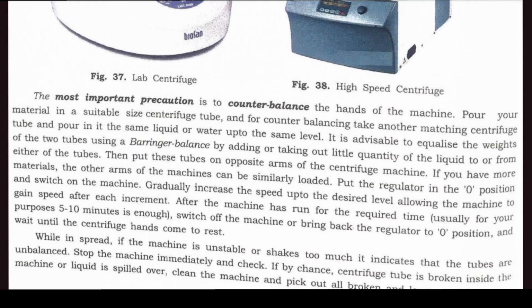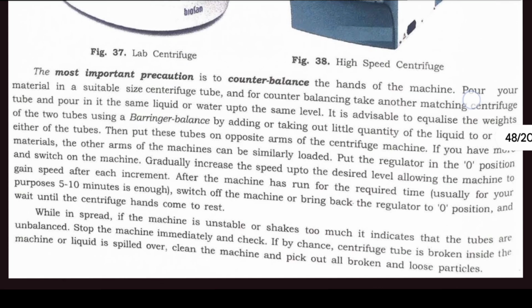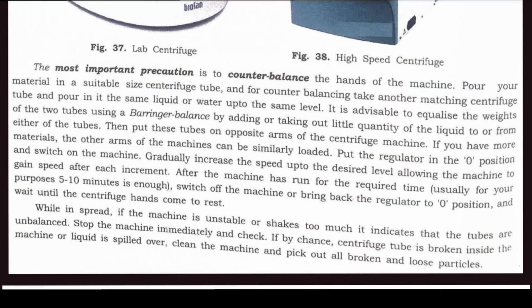While gaining speed, if the machine is unstable or shakes too much, it indicates that the tubes are unbalanced. Stop the machine immediately and check if by chance a centrifuge tube is broken inside the machine or liquid is spilled over. Clean the machine and pick out all broken and loose particles.